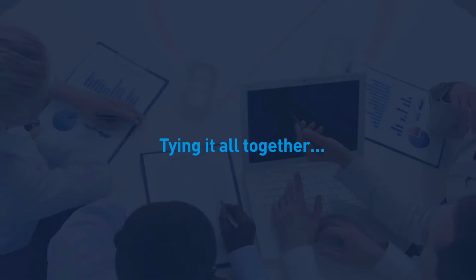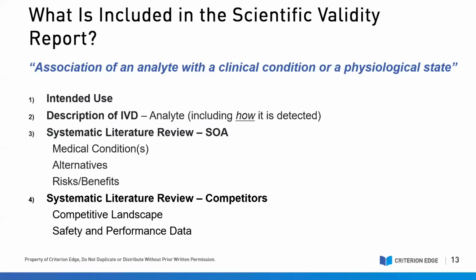If you've designed appropriate templates, your PER should start at the beginning by setting the stage with the state of the art, and your story flows from there. The PER should culminate with your conclusion that yes, indeed, this PER has demonstrated that your IVD is safe, it performs as intended, and may be considered state of the art, which means it meets the IVDR requirements for safety and performance. So now we're going to take a look at some of the critical components within a typical SVR template and really look at how the SOA section fits into that. That being said, the template will certainly vary, and it will need to be customized based on the unique needs of your device.